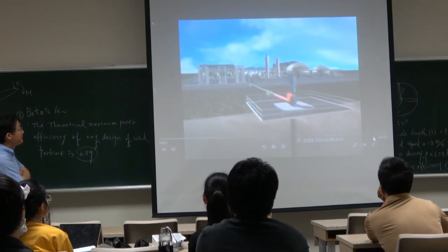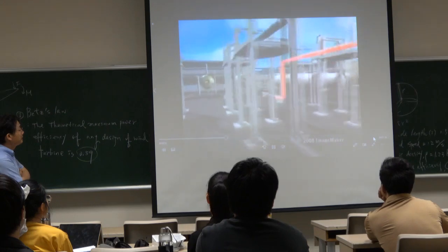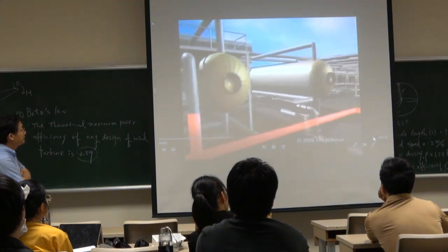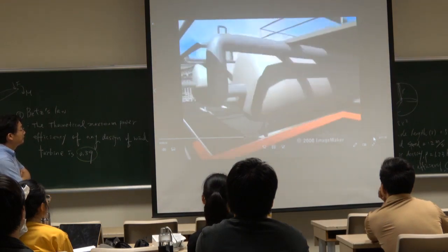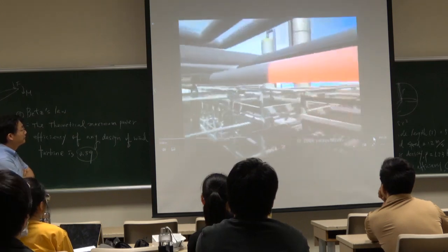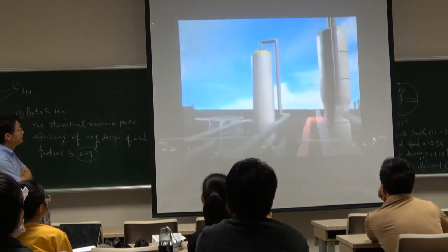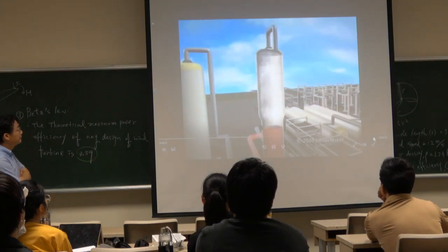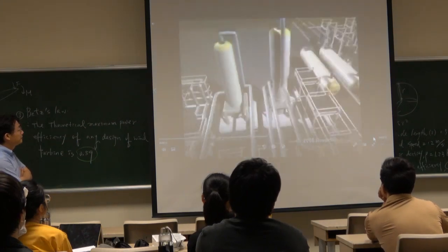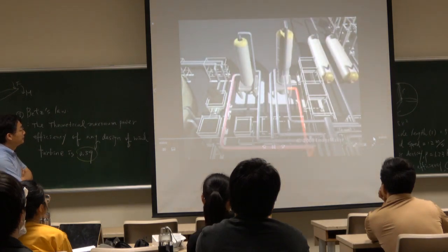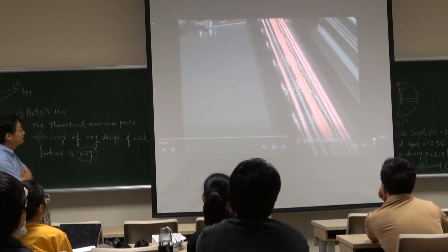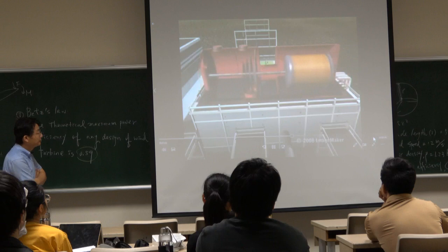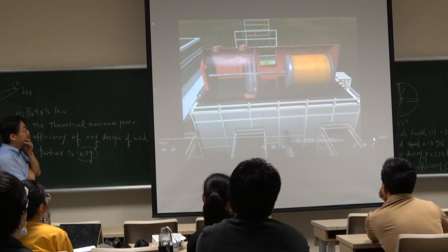Together, the hot fluid and steam move through a surface pipeline to a wellhead separator, where the pressure is reduced. Here, most of the fluid vaporizes and flashes into high-pressure steam. Any fluid not flashed into steam moves to a standard pressure crystallizer to produce standard pressure steam. Remaining fluid is then flashed at a lower pressure to create low-pressure steam. All steam created in the plant is sent to a turbine on site. The force of the steam spins the turbine's blades, which turns a shaft connected to an electrical generator.